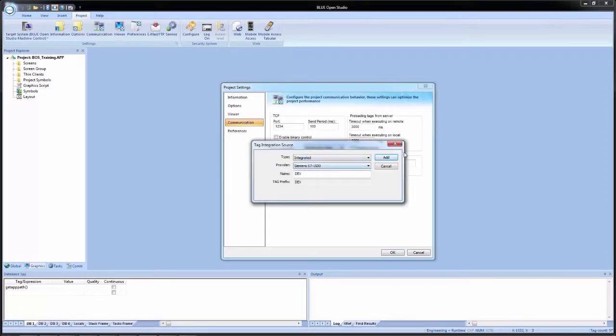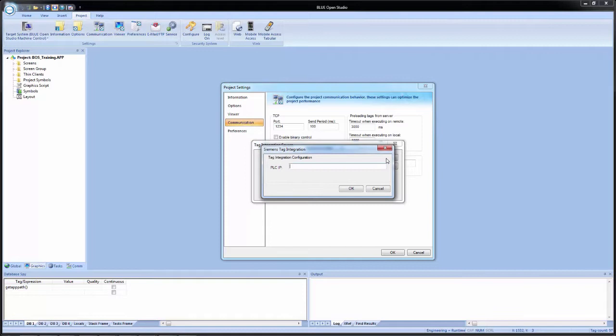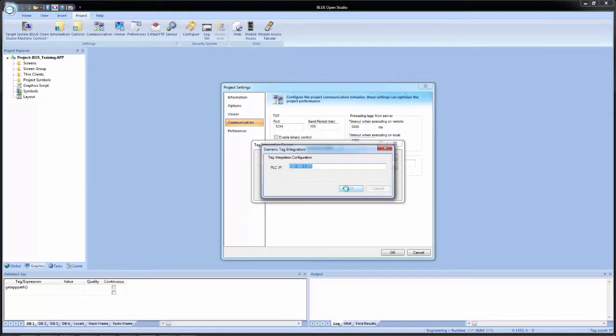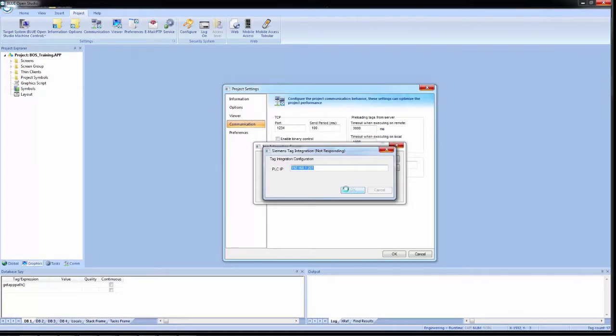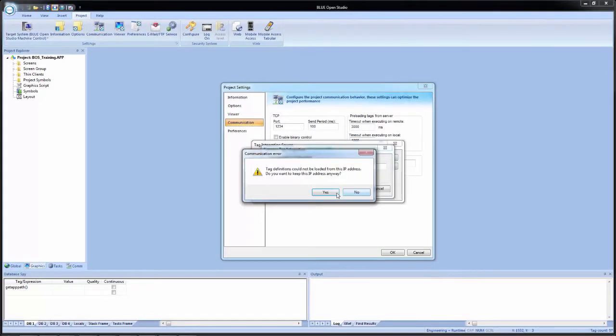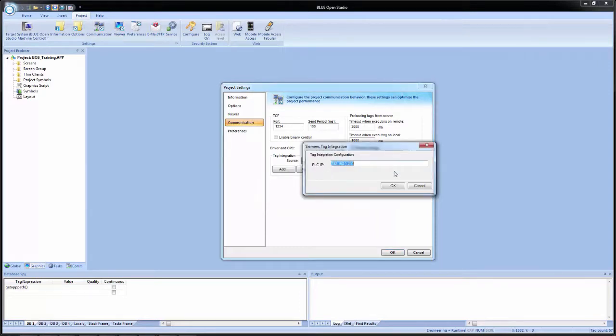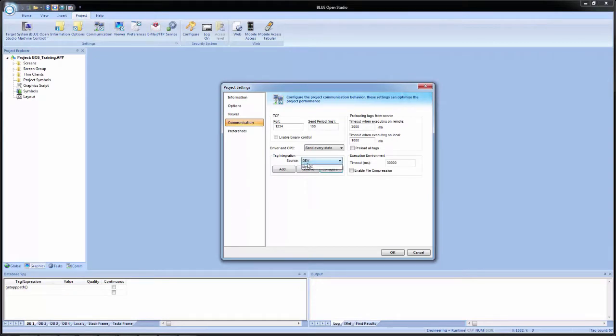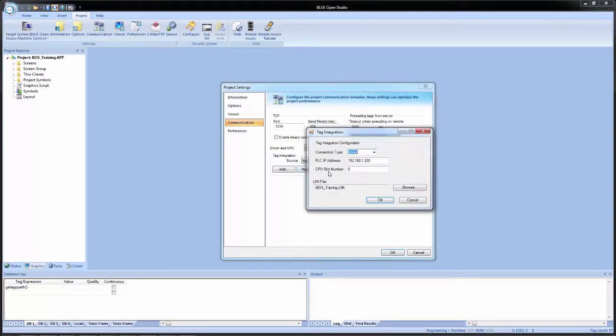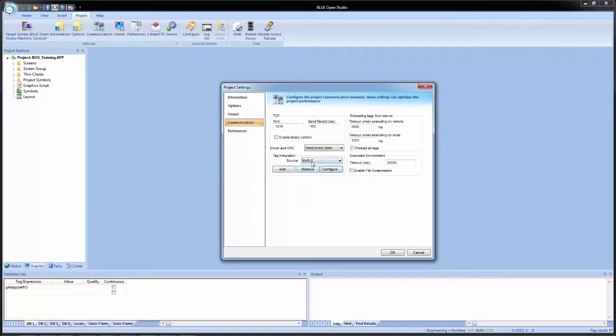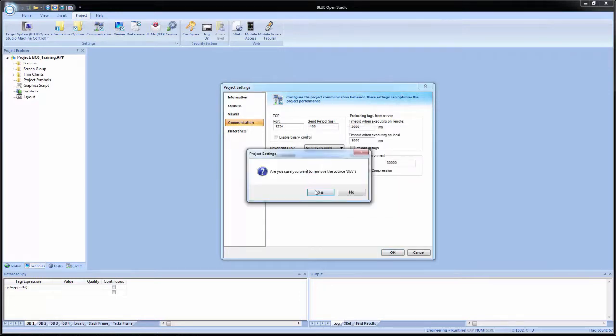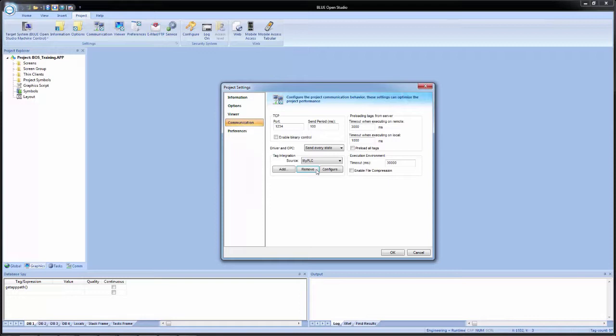and I wanted to do Siemens and leave it at dev, if I click add, if I put in the IP address, click OK, right now it's going out and attempting to communicate. It obviously won't find anything. We can add it anyway. And now you see that we have two. So if I click on dev, I can come back into configure and change the settings for that. If I select my PLC and go into configure, now I can change the settings for that source. So in this case, we don't need dev, so I'm going to select it and remove. Click yes. And now I only have my one.